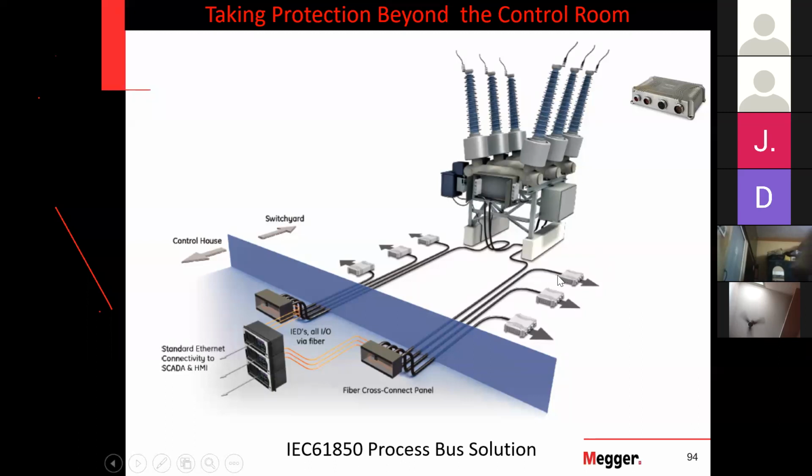And this being a military standard cable, animals cannot bite this cable. And this is an IP66 device. So this is totally enclosed. So there is no disturbance and there is no kiosk also. So all the disadvantages which we saw earlier are overcome. And at the same time, we also have all the advantages which we saw earlier. That is elimination of copper cable from control room to switchyard. So this is called the process bus system.